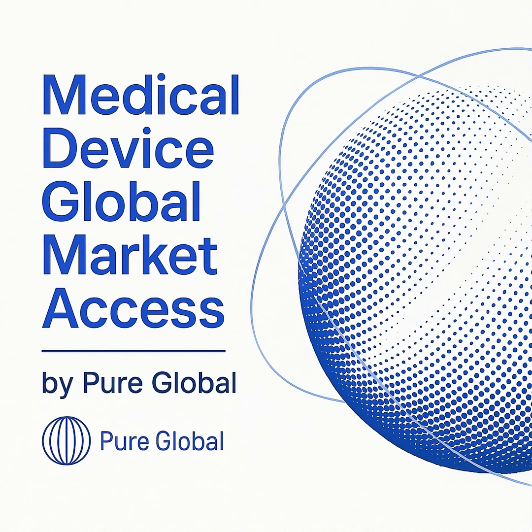Unlike the FDA's 510(k) or PMA routes, the MFDS has three distinct pathways. Class 1 devices require a simple pre-market notification. Class 2 devices, as they have a predicate device already on the Korean market, can go through a pre-market certification process, often reviewed by a third party. However, novel Class 2 devices, along with all Class 3 and Class 4 devices, must undergo a full pre-market approval, which involves a comprehensive review directly by the MFDS.